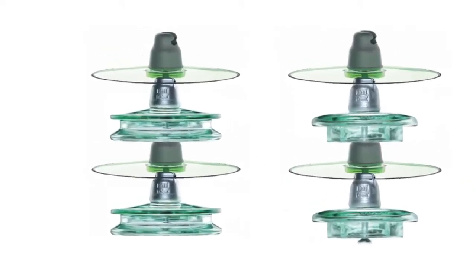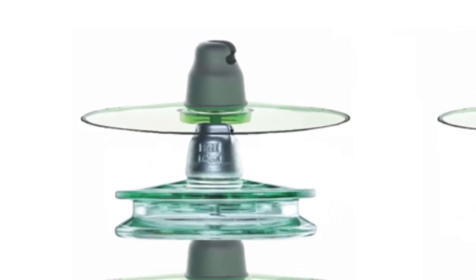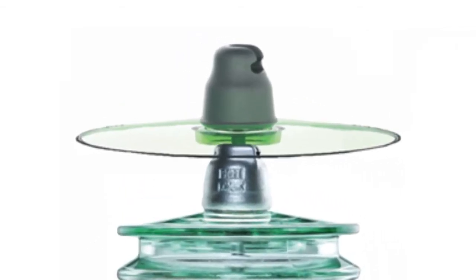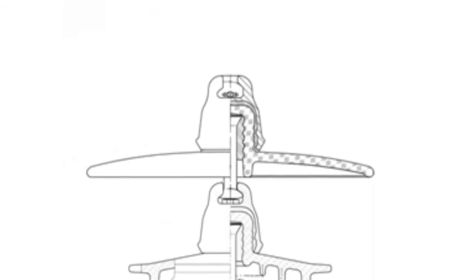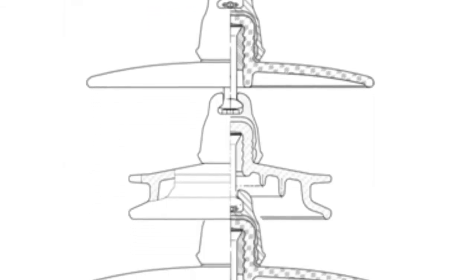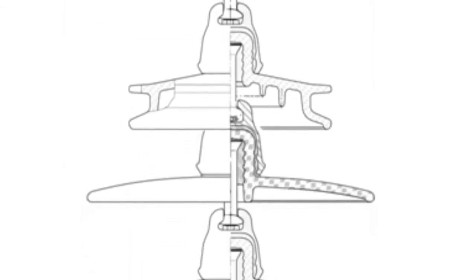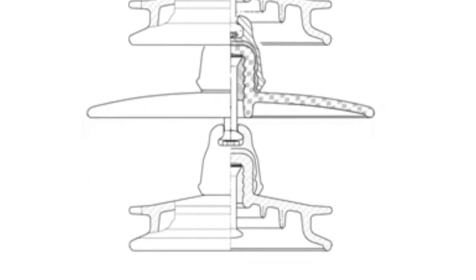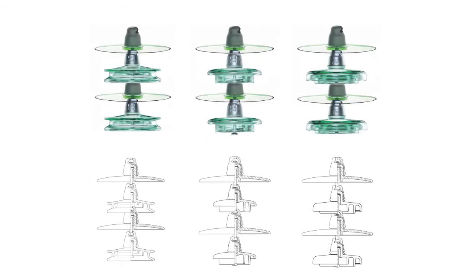Number 1. Aerodynamic profile is designed for easy air blow-off, which contains dust, to prevent from dust fall, and also it is easily self-cleaned by wind and rain. It is good for dry dust deposits. It has a huge creepage distance. Number 2. The insulators of fog type with extended ribs also have huge creepage distance and are designed to prevent moist liquid contaminations.